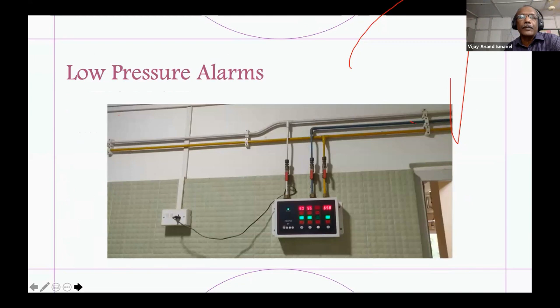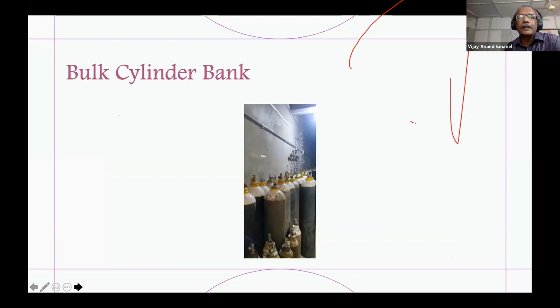And we need piping, copper pipes. You can also use a flexible pipe if there is a gap between buildings. And we need a low pressure alarm and automatic changeover. The moment the pressure drops, it should change over to cylinders. So that is a pressure alarm. These should be kept at the end user points like the ICU and places like that. And this is the automatic changeover switch. I've also shown the flexible piping in case copper is not available, and the cylinder bank.